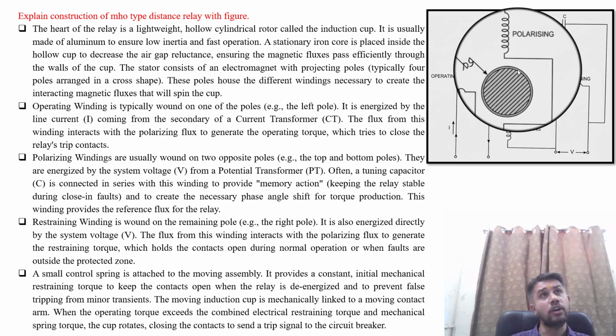When the operating torque exceeds the combined electrical restraining torque and mechanical spring torque, the cup rotates, closing the contacts to send the trip signal to the circuit breaker. So this is the basic detail about the construction of the mho type distance relay.